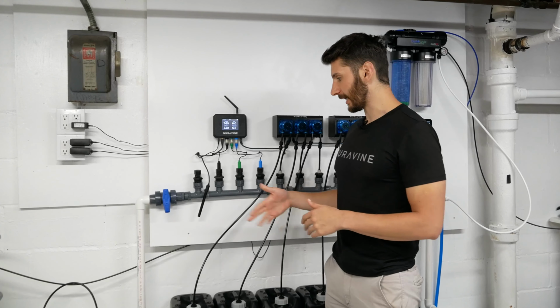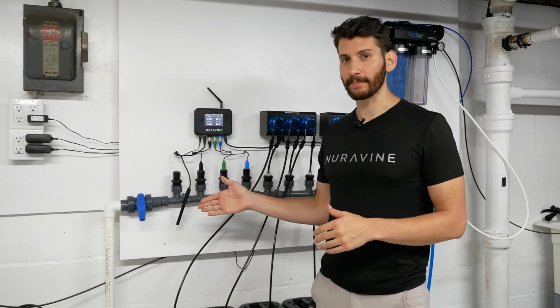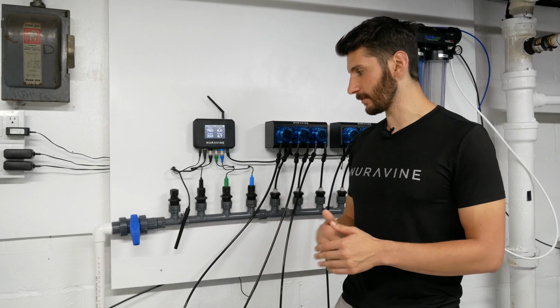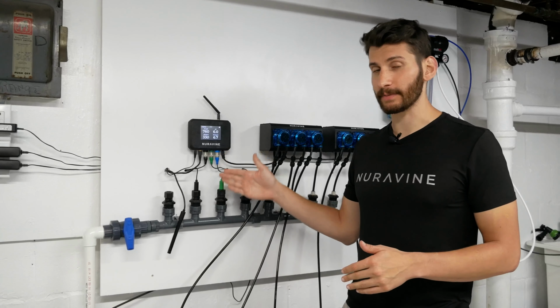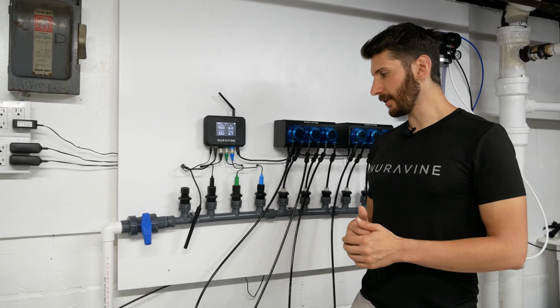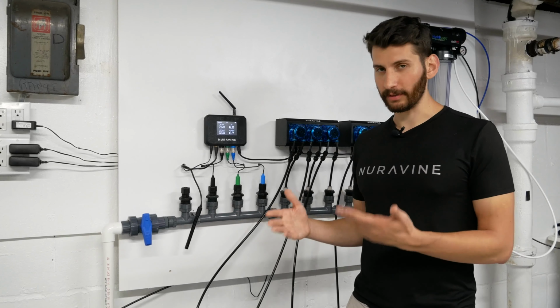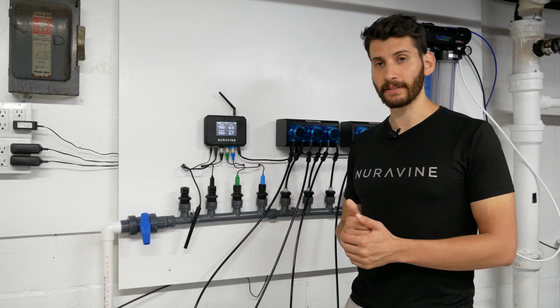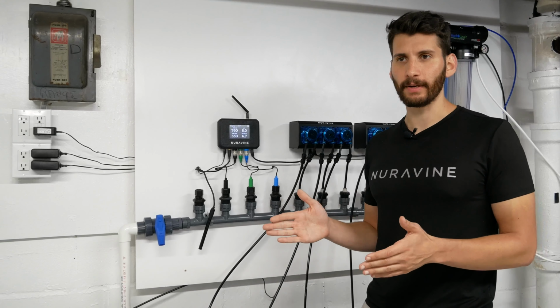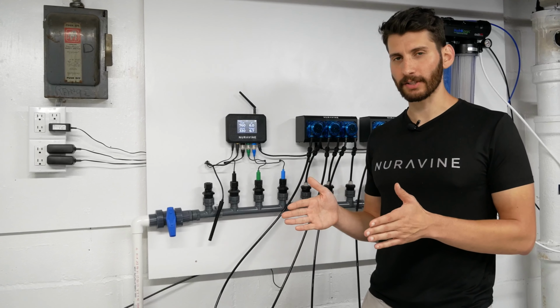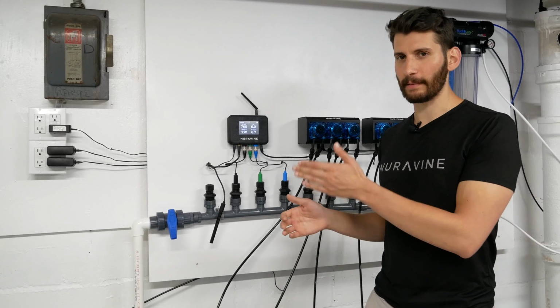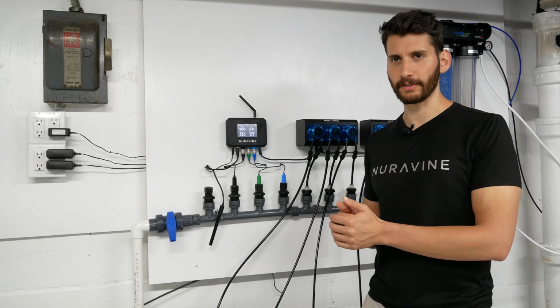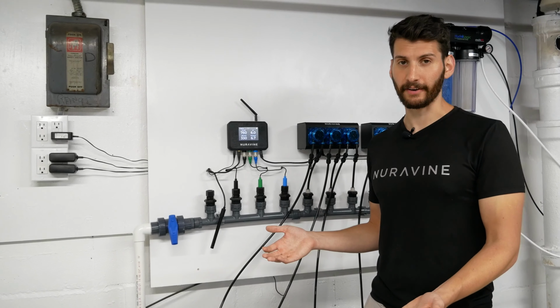One thing I want to note is I actually left the EC probe out of the holder because we're going to need that probe as part of the pH calibration. The reason is because the EC probe is not only for EC, it also has temperature built into it. And so when you're calibrating the probe, the calibration value changes based on the temperature, but by using a temperature probe, it can compensate for that temperature, so it's always going to be 100% accurate.